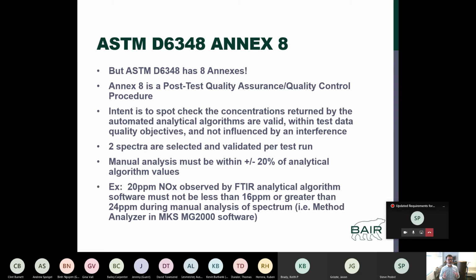That 8th annex is a post-test quality assurance quality control procedure. It's intended to spot check your concentrations returned by your software, your data acquisition software that has the analytical algorithms that are all part of your FTIR usage. It proves that your test data meets its quality objectives and that you don't have any interferences at play here. So per test run, you select 2 FTIR spectra, so essentially 2 samples per run, 1 minute per sample over the course of a 60-minute run or 30-minute run for a PBR test in Texas, or if you're going to use this on a turbine under a Quad K, you have to select 2 samples. You get 1 sample that is close to the average of that test run, and then you find 1 sample where you've got an outlier.